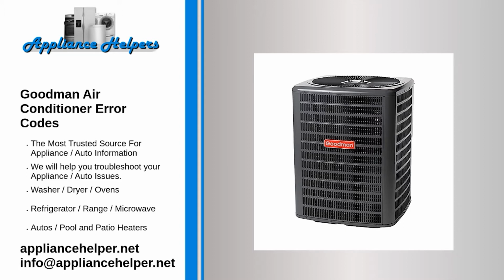Code D0, problem: the air conditioner heat pump is wired as part of a communicating system and the integrated control module does not contain any shared data. Code D1, problem: the air conditioner heat pump is wired as part of a communicating system and the integrated control module contains invalid shared data or network data is invalid for the integrated control module.